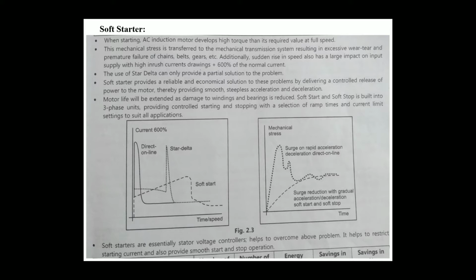The use of star delta can only provide a partial solution to the problem. Soft starter provides a reliable and economical solution to these problems by delivering a controlled release of power to the motor, thereby providing smooth, stepless acceleration and deceleration. Motor life will be extended as damage to winding and bearings is reduced. Soft start and soft stop is built into the three-phase unit. It provides controlled starting and stopping with a selection of ramp times and current limit settings to suit all applications.